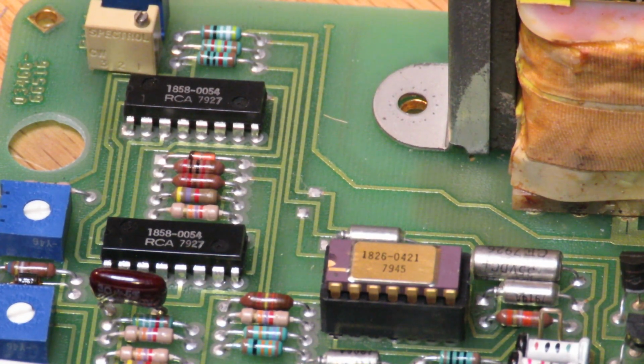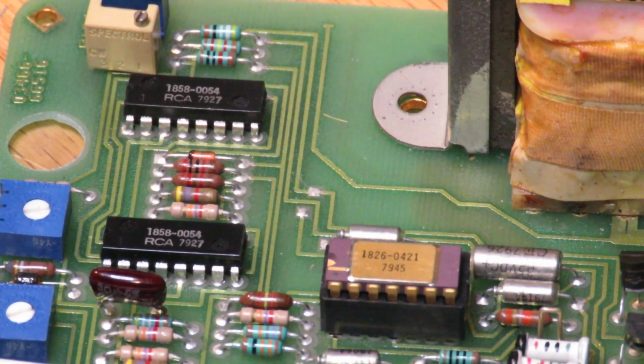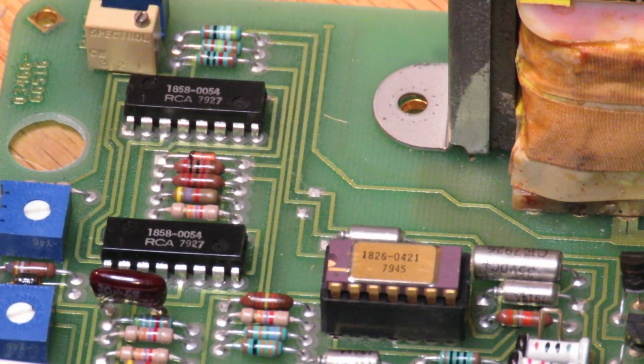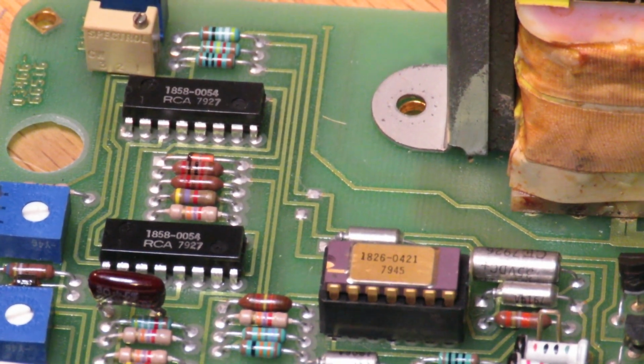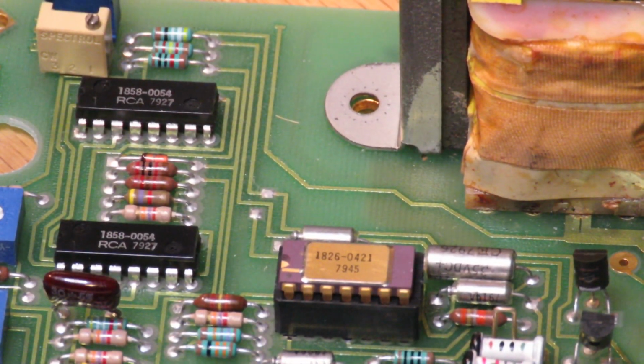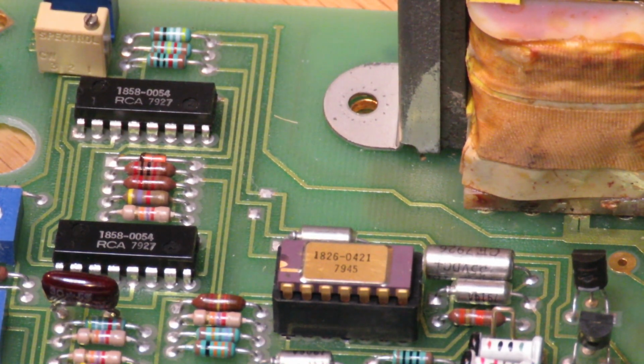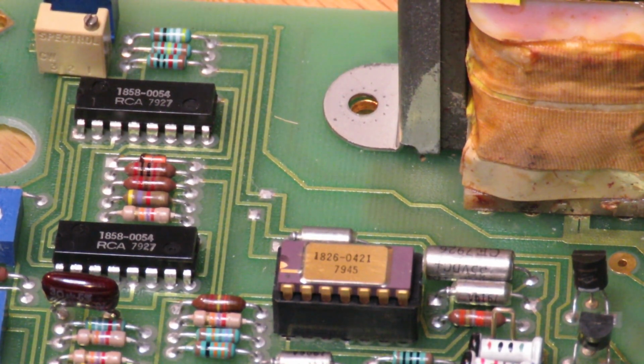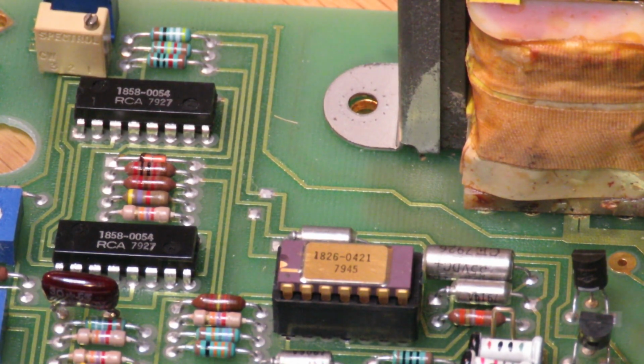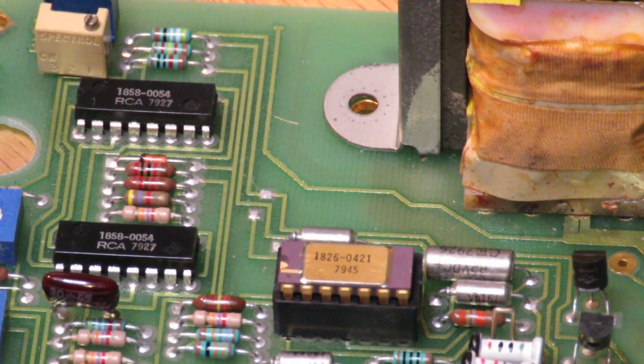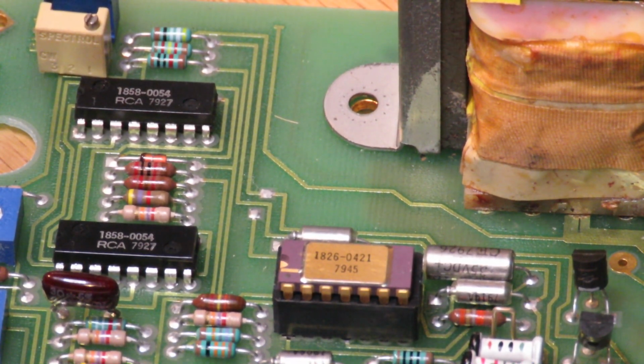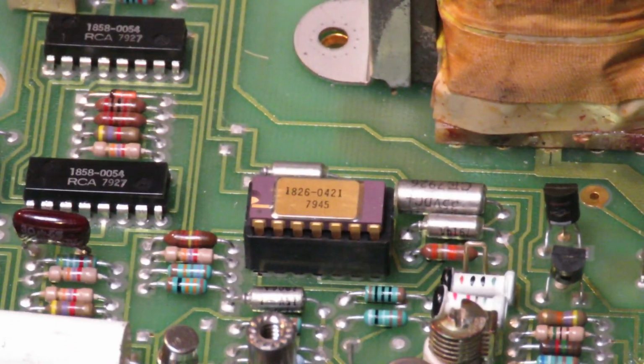I'm 99% sure that it's dead, and 90% sure that when I fix it, the functionality of the meter will come back. Because if the comparator is stuck high or stuck low, which it is, it can't control the feedback loop and fails immediately - can't auto zero, can't do any of its standard functions. Everything fails. So yeah, I'm pretty sure that's the second problem.